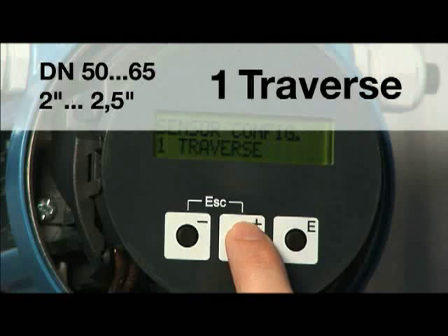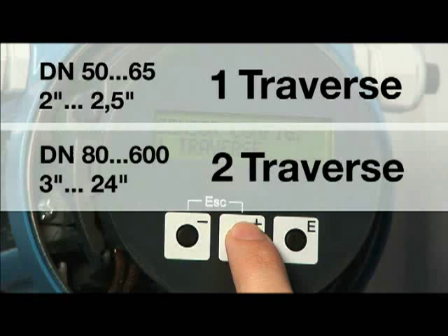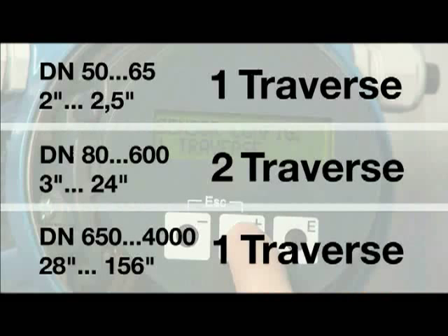For pipes smaller than 80 mm, one traverse is suggested. For pipes in the size range of 80 mm to 600 mm, two traverse installation is suggested. And for pipes larger than 600 mm, one traverse is suggested.